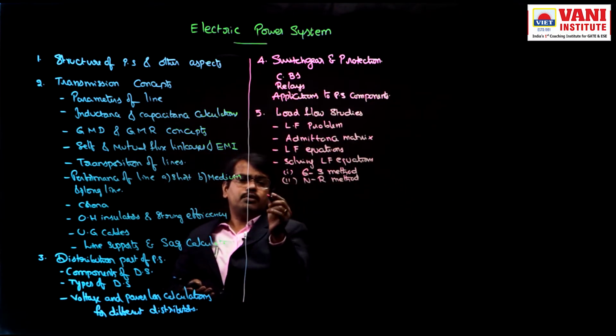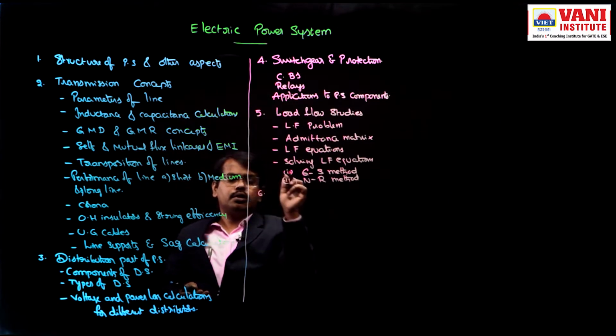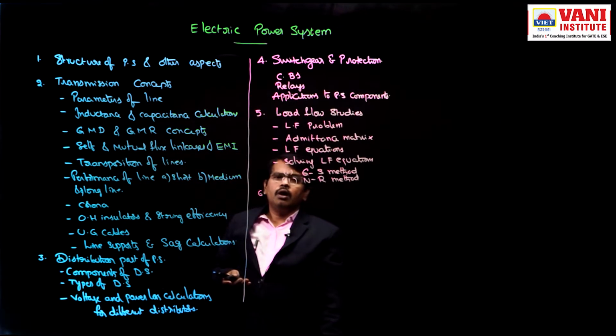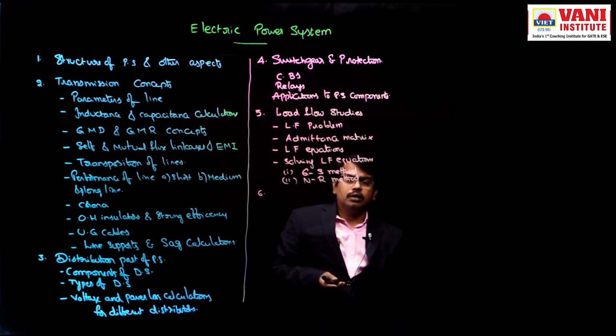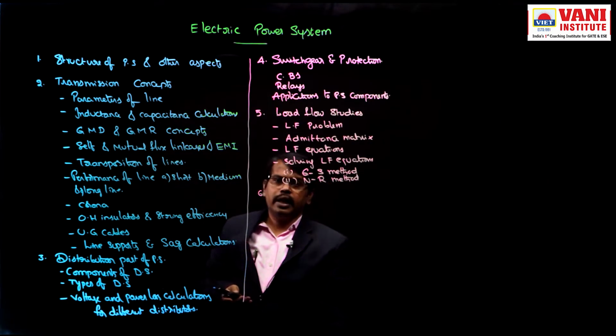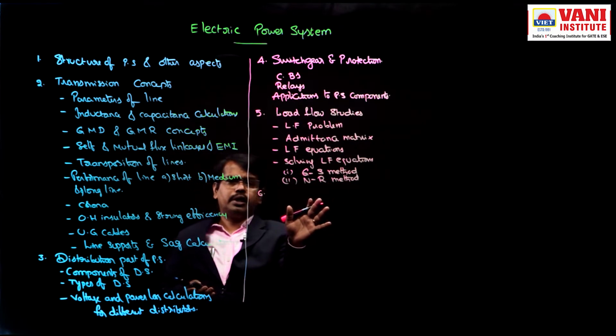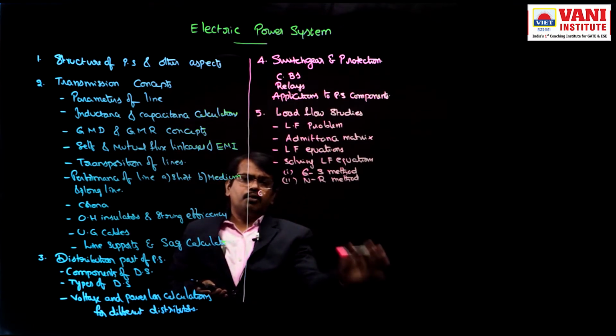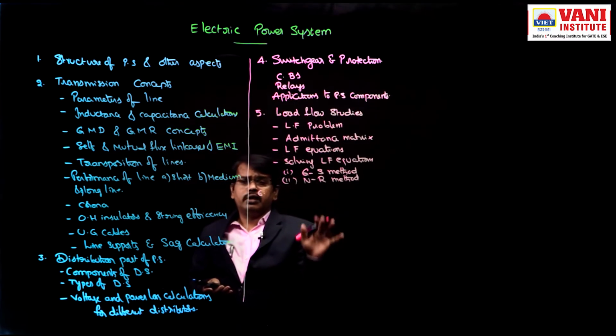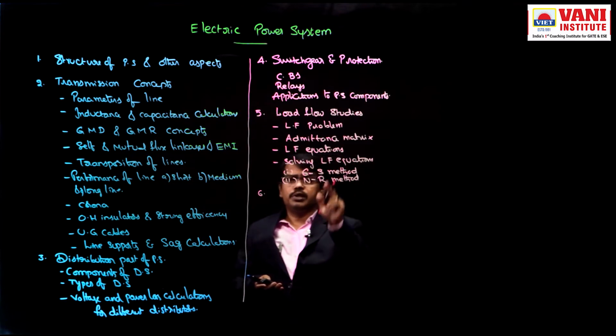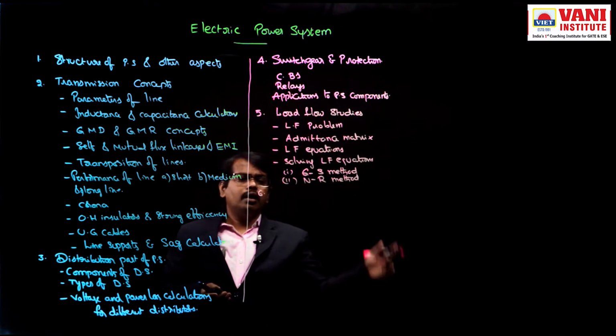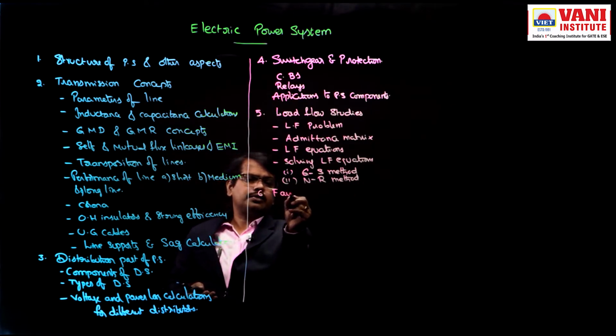Once load flow is completed, we can start either fault analysis or stability. Either can be started, but before starting fault analysis or stability, load flows must be done. So, fault analysis.